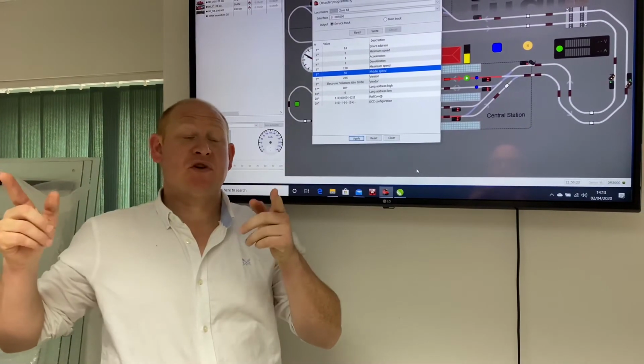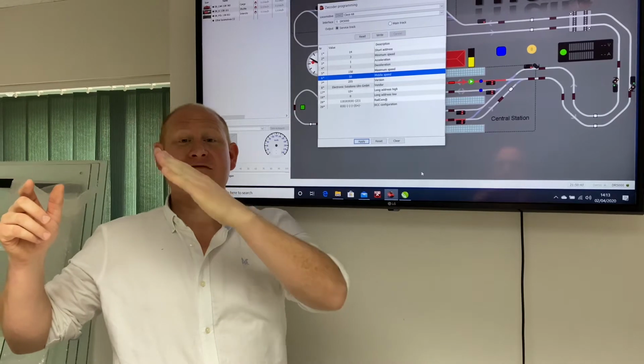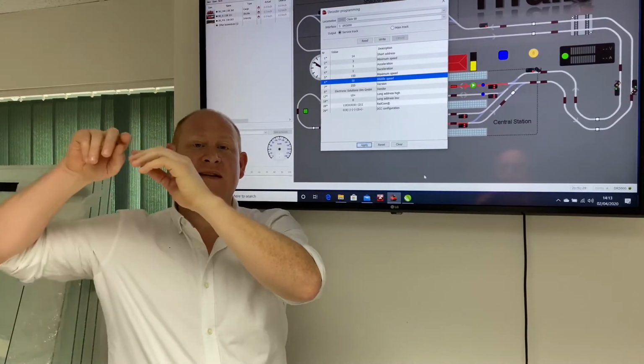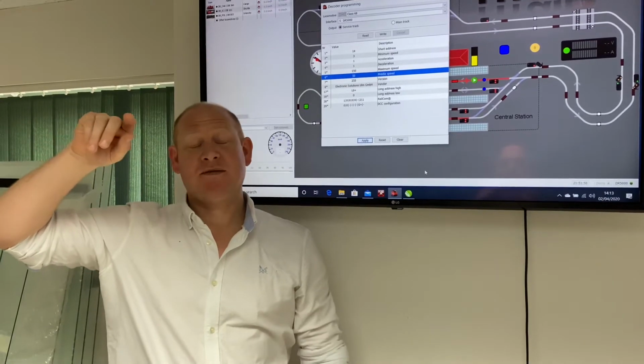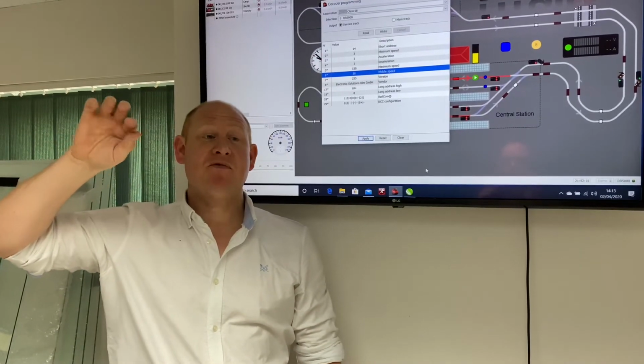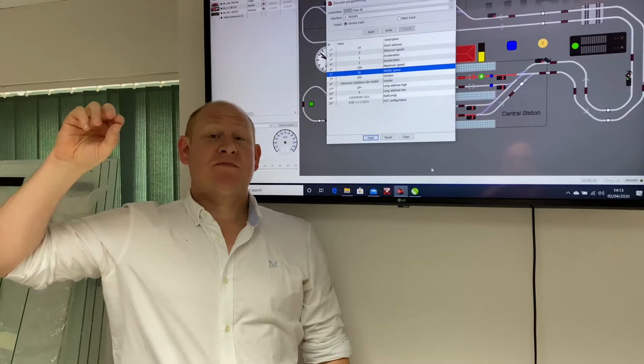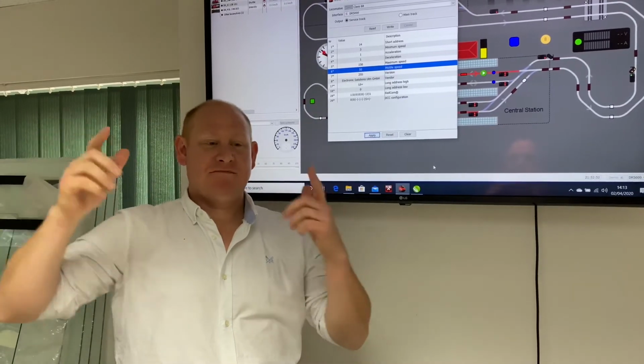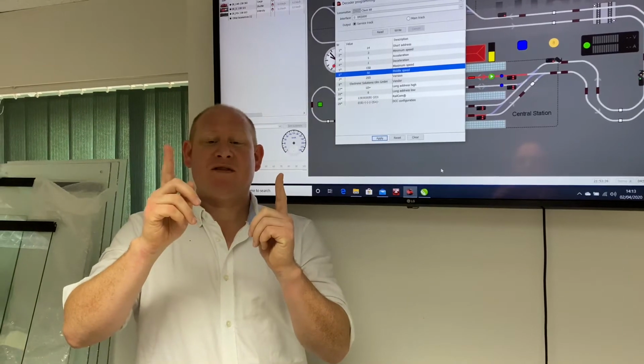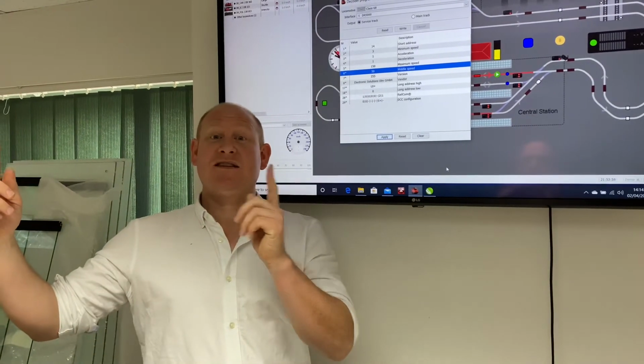detectable section to record the speed, it might still be accelerating, ramping up to the actual speed step that we're trying to record. So then when it gets halfway through the speed calibration zone, it will only have just got to the speed step's correct speed. So then that speed step's wrong, because it would have taken half of the feedback at one speed and the rest of the feedback at the true speed.